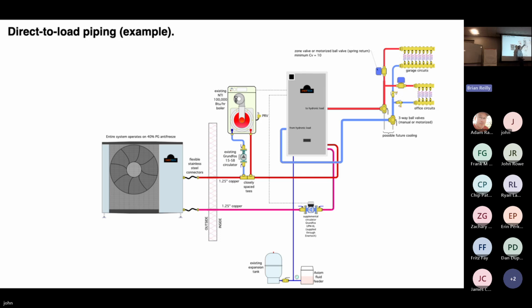There's another circulator in this box. If you take this one away, the circulator that's in the box, well, there is a circulator on the boiler too, but the same circulator that's in the box pushing flow through here is also pushing flow through the distribution system. It's an interesting idea. I think it will work in many applications. I still think there are applications where a buffer tank makes sense, and I'll give an example.